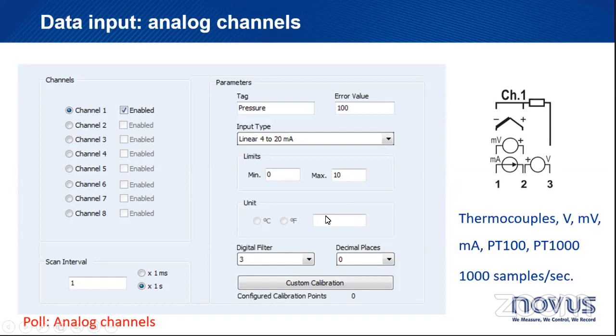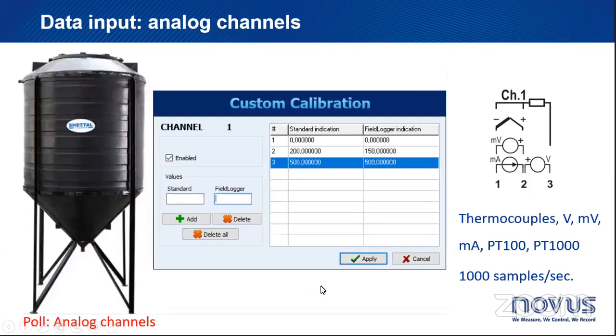And there is another very nice feature on the FieldLogger, which is custom calibration. What is custom calibration for? So imagine any process or measurement that is not linear, okay? I brought this example here because it's the simple one. This example is measurement of level in a tank that has a conical bottom, for example. So here is a conic tank and you see, level is not linear or volume is not linear throughout the tank. It's different depending on the height. So in that case, you want to input your own curve, your own numbers.